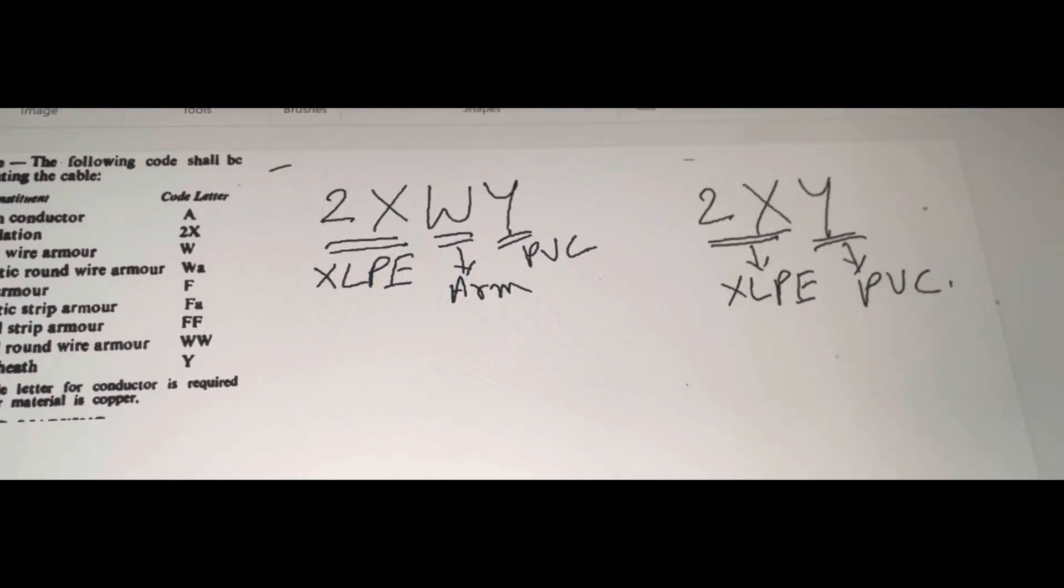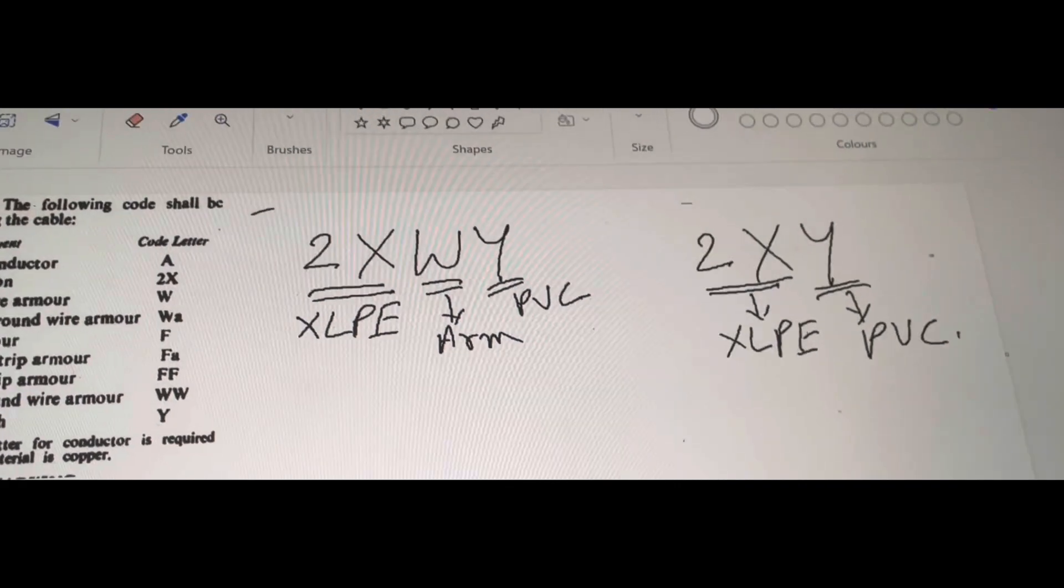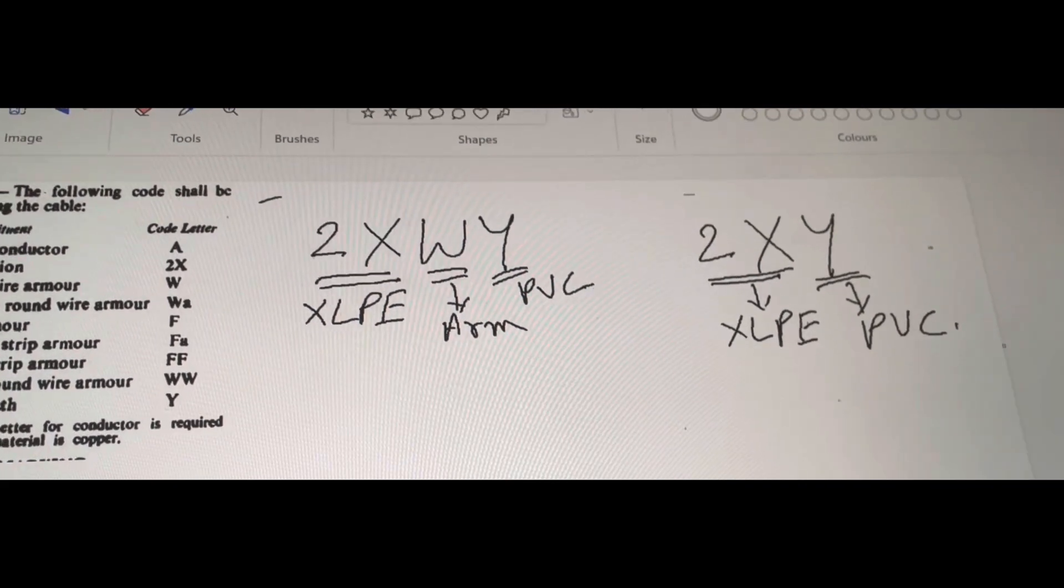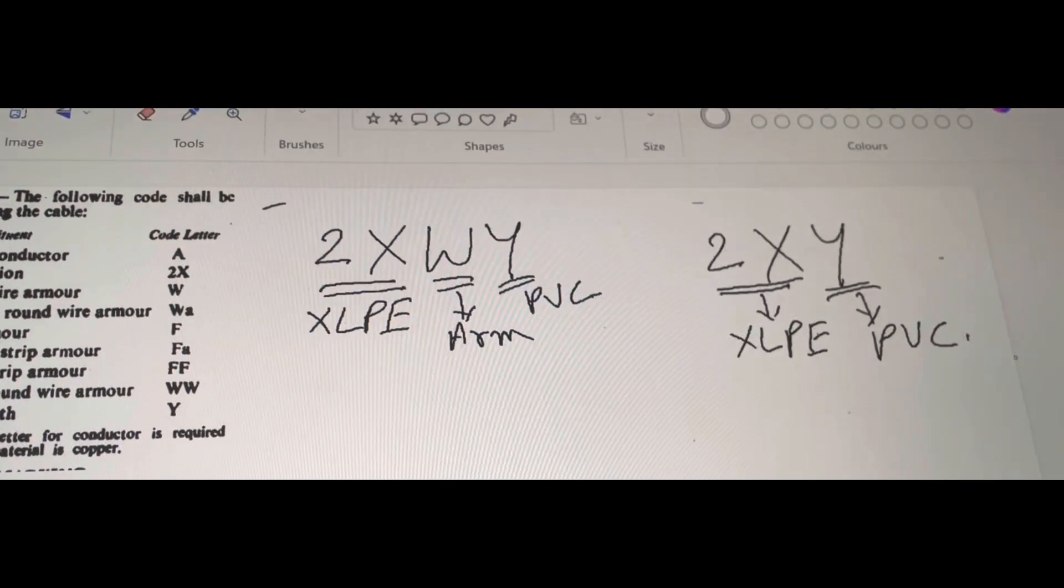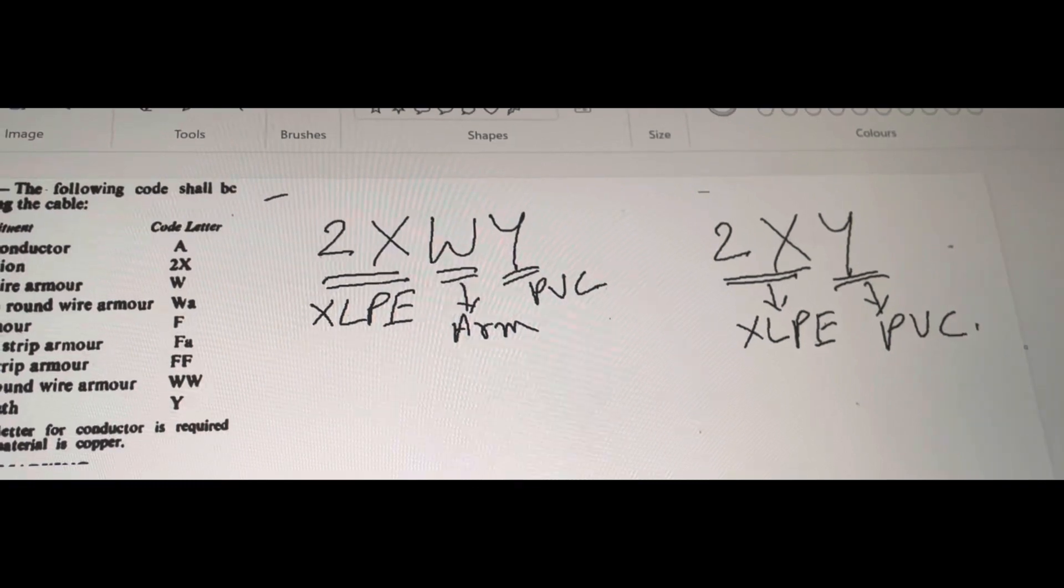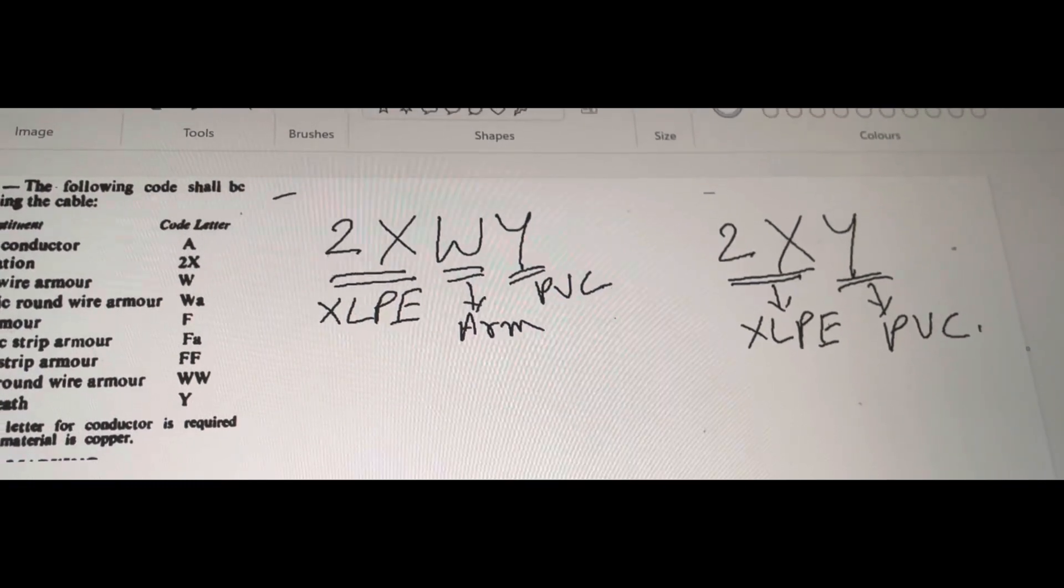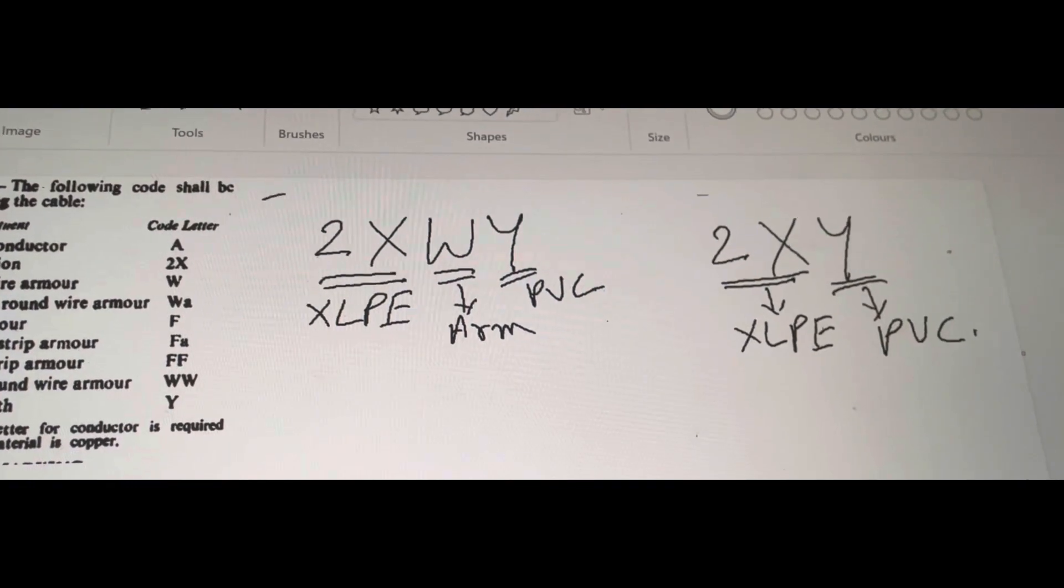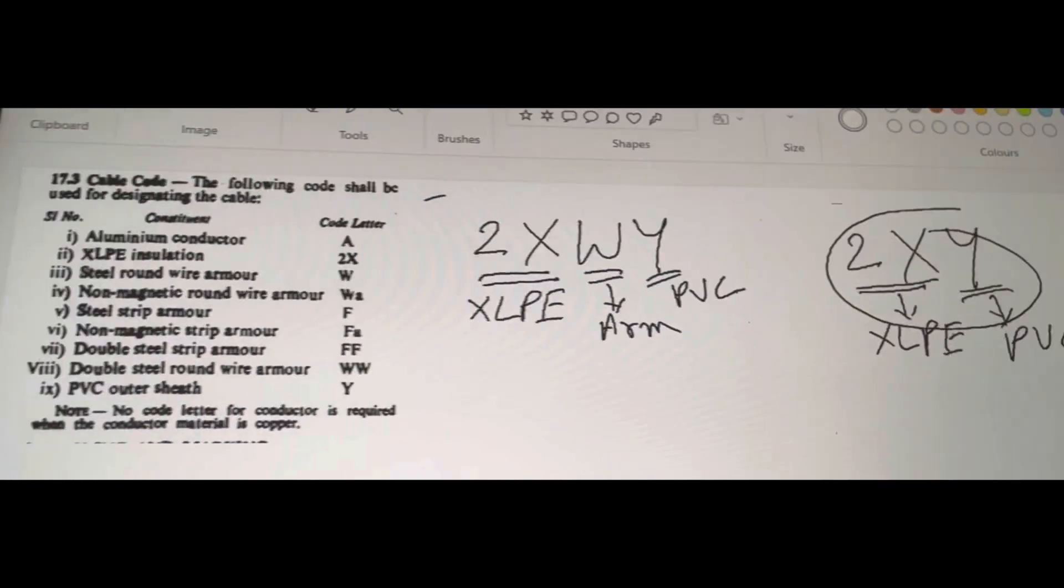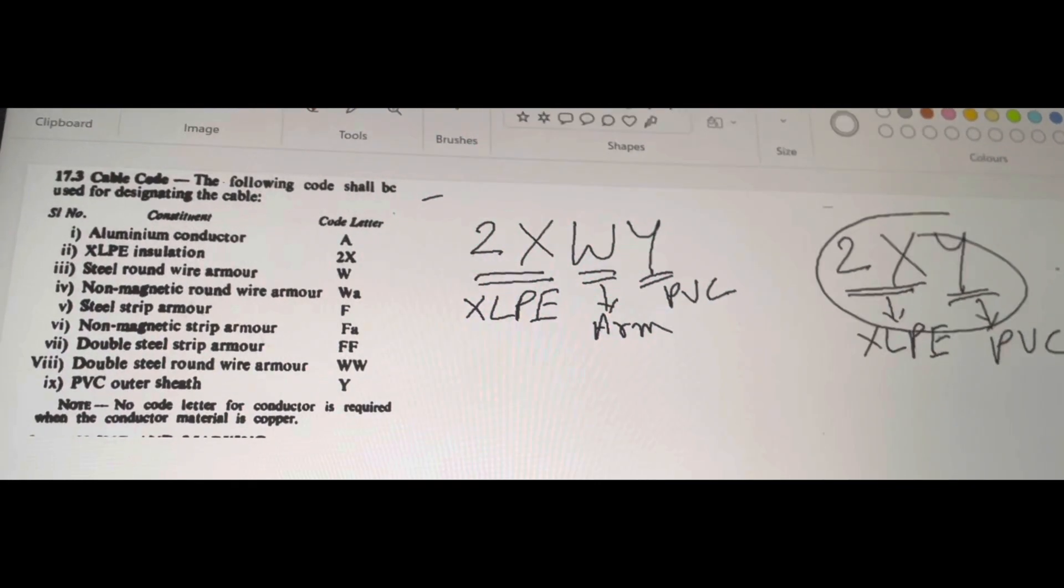And you can observe that there is no letter called w in this particular code. The meaning is there is no armoring present in this particular cable. As there is no letter called w we can assume that there is no armoring present in this particular cable. So, this is the way to interpret this particular cable code.